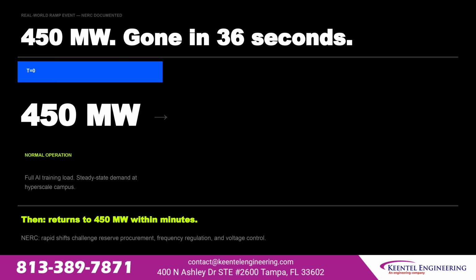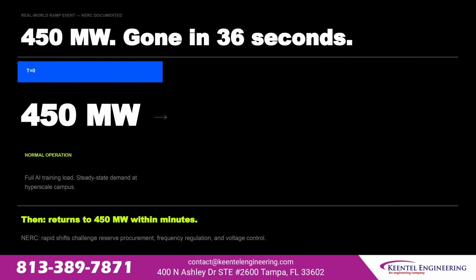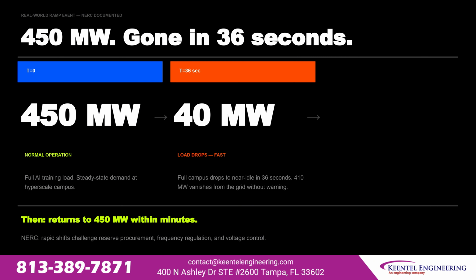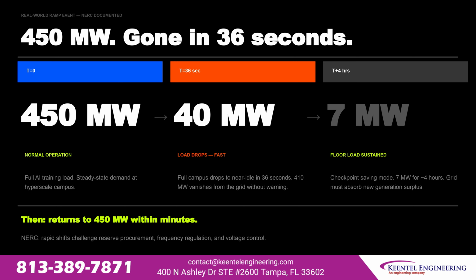NERC documented this. At time 0, 450 megawatts, full AI training load at a hyperscale campus. Steady state demand at 36 seconds, 40 megawatts. The full campus drops to near idle. 410 megawatts vanishes from the grid without warning. 4 hours later, 7 megawatts. Checkpoint saving mode, sustained for 4 hours while the grid absorbs a new generation surplus it wasn't expecting. Then the campus returns to 450 megawatts within minutes. NERC's conclusion: rapid load shifts challenge reserve procurement, frequency regulation, and voltage control simultaneously. This is a single facility, one event, 450 megawatts.